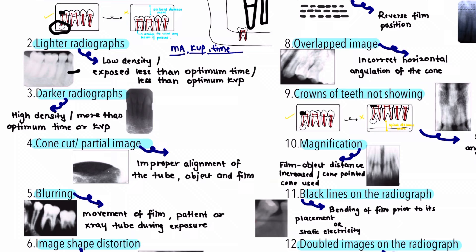The third error is darker radiographs, which appear more blackish in color due to high density. This is the complete opposite of lighter radiographs — darker radiographs result from over-exposure, meaning the radiograph is exposed at higher mA, kVp, or time. The correction is to use appropriate mA, kVp, and time. Another reason can be if the source-to-film distance is too short, whereas in lighter radiographs, the source-to-film distance is longer.